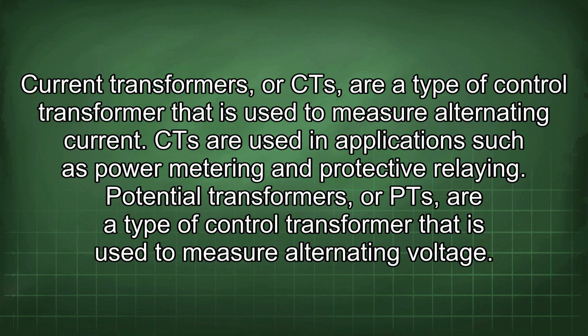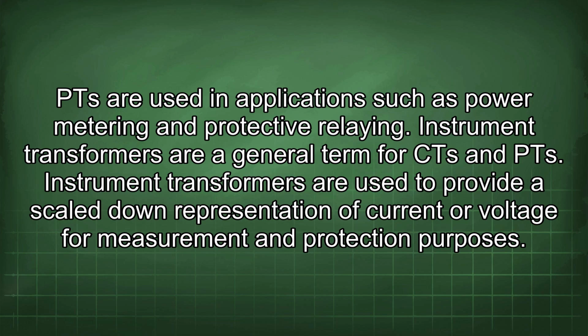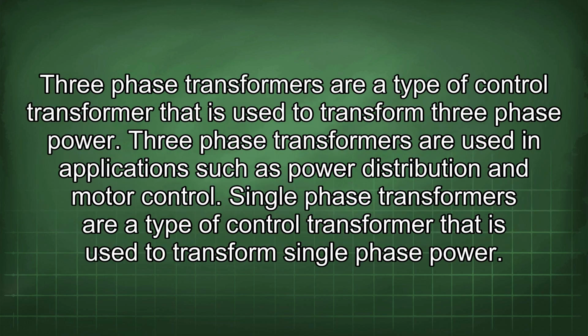Potential transformers, or PTs, are a type of control transformer that is used to measure alternating voltage. PTs are used in applications such as power metering and protective relaying. Instrument transformers are a general term for CTs and PTs. Instrument transformers are used to provide a scaled-down representation of current or voltage for measurement and protection purposes. Three-phase transformers are a type of control transformer that is used to transform three-phase power. Three-phase transformers are used in applications such as power distribution and motor control.